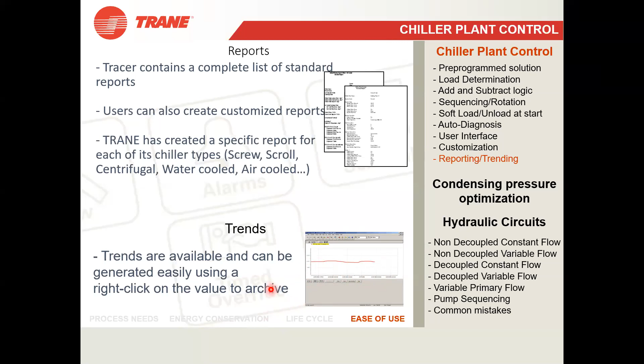Now I'm going to one very important thing: by using this chiller plant control, you can also do condensing pressure optimization. What is condensing pressure optimization? This is also a very, very important thing. I am sure that everybody understands the basic chiller function. So I'll just say that when refrigerant is passing through the compressor, the condensing pressure means the refrigerant pressure inside the chiller compressor. The more you decrease this pressure, the less energy the chiller will use.